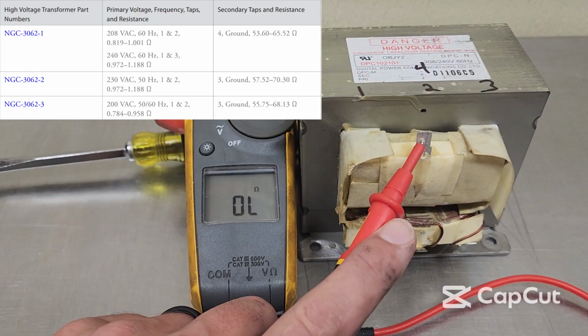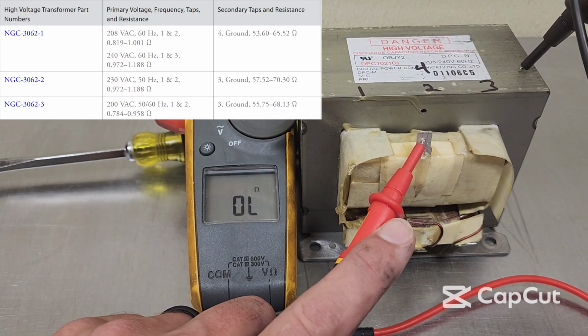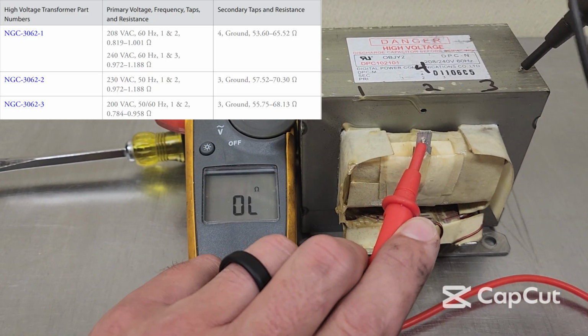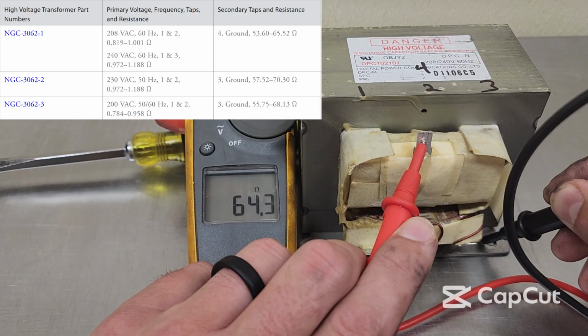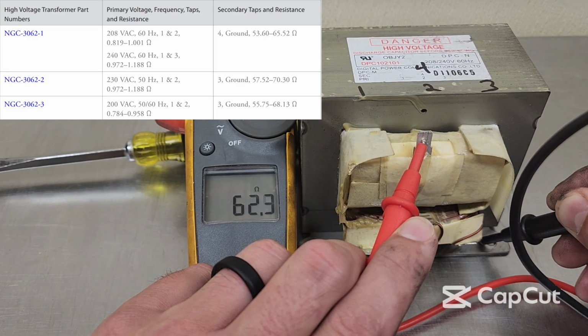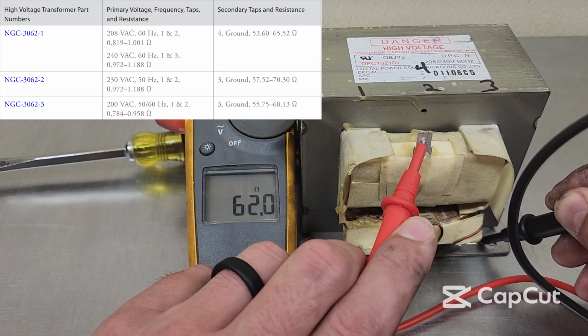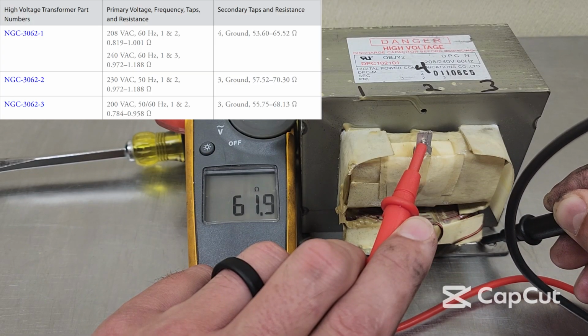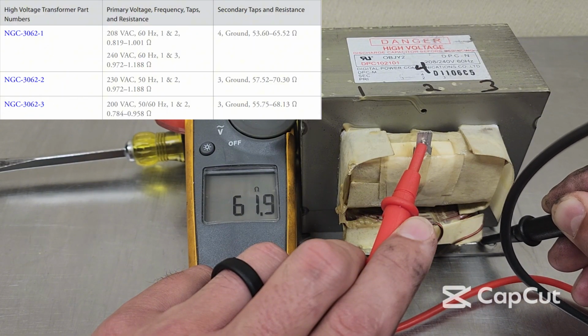And this one is tested 4 to ground, and we should get a value. There we go. Find a real ground. And we are looking for anywhere between 53.6 ohms to 65.52 ohms to ground. So in this case, we are 61.9, which is totally normal.